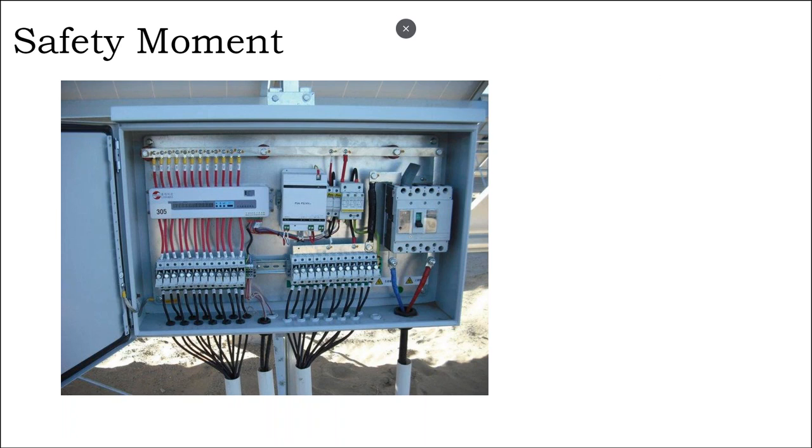to make our inverters be in a floating architecture. The way it used to be, and the way it still is on some battery inverters, is this negative side here would get connected to ground and you'd only fuse the positive sides, and that could cause a ground fault where one circuit, for whatever reason, starts faulting to ground and other circuits join in. And then that starts raising the voltage of ground. And so the inverter, looking at the ground voltage versus the voltage of the system, doesn't see the fault.